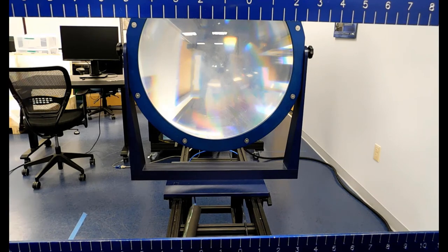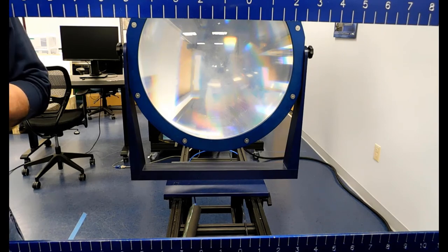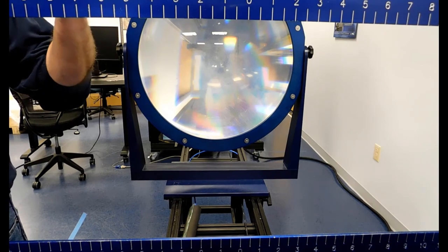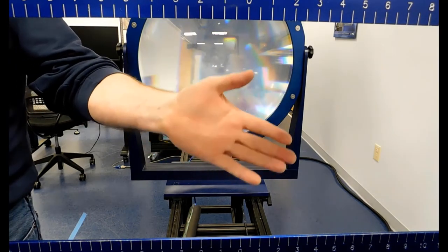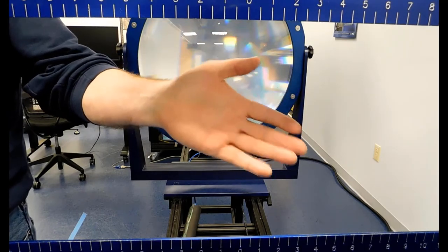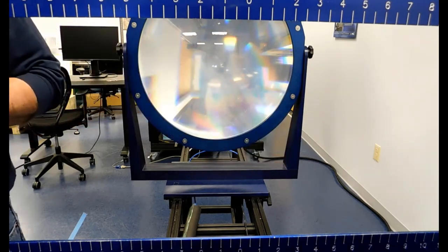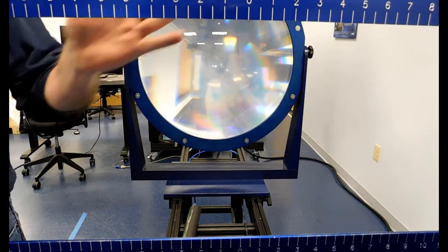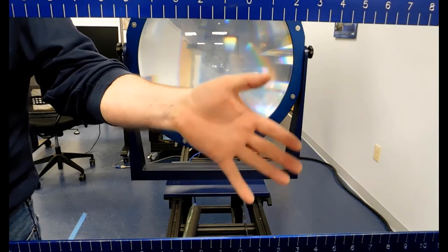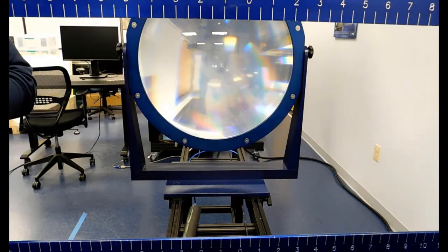Before I mount it let me first talk about calibration. When we calibrated we first measured no sample at all which is what you see here. It's air and so it has a hundred percent transmission and no reflection. We then also placed a metal plate in here which has a hundred percent reflection and no transmission.